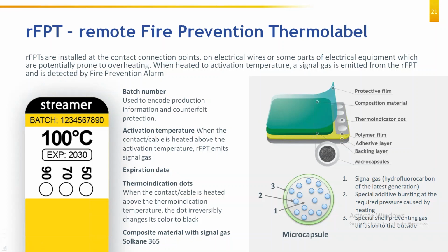One question nobody asked: in a particular cabinet, if there are, for example, 15 stickers and you get an alarm from that cabinet, when you go and visually inspect, how will you know which particular sticker has operated? The reply is, the first indication is that in that particular sticker all three dots will be black, and the second indication is that the yellow part of that sticker will get physically damaged. You will be able to see physically that the yellow part is damaged. So these are the two ways in which we can detect which particular sticker has operated.